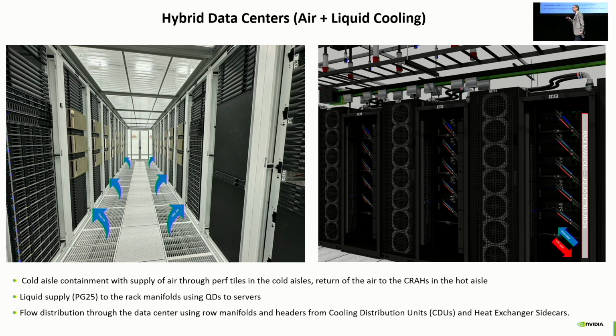...you're going to be limited by the physics of air removal. I can remove heat any day of the week, up to 100 kilowatts per rack, even more with air cooling. The problem is the limitation is size. My racks are limited to a certain size. Data centers are basically building blocks that have been around for 70 years with air cooling.